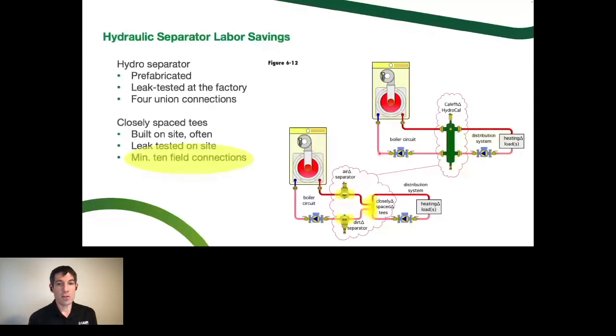Okay, I mentioned earlier that the closely spaced tees were the least expensive way to do primary, secondary piping, if you count labor. So unless somewhere up in Canada you have somebody that can solder up this entire system, or press or whatever connection style you use, for $5 Canadian an hour. I'm sure that's well below the minimum wage anyway, but if you could find somebody that could put that together, or your niece or nephew could do that for you at that price, go for it. That would be a less expensive thing to do, even buying an air and dirt separator.